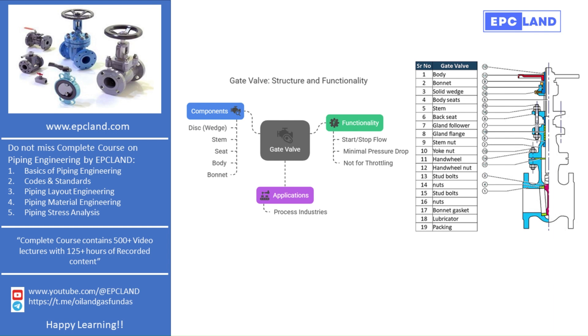One important point to remember is that gate valves are not meant for controlling or regulating flow. They are designed to be either fully open or fully closed. If you try to use them in a partially open position to control flow, the fast-moving fluid can cause damage to the disc and the seat inside the valve. This can also lead to vibration, noise, and wear over time.